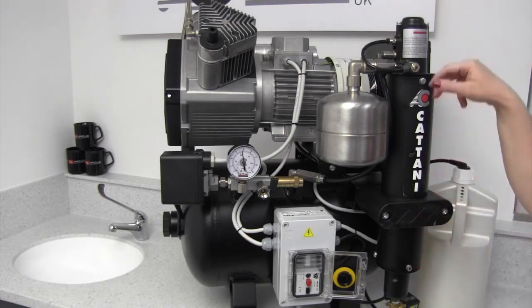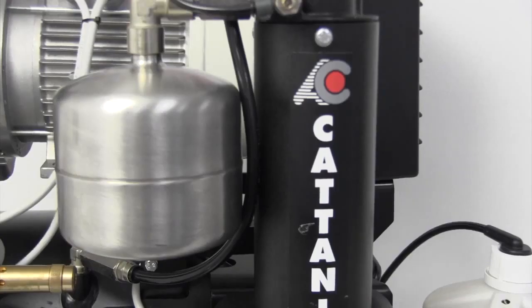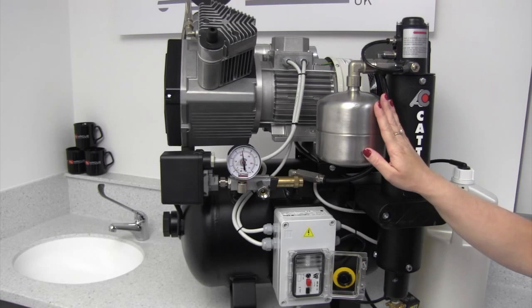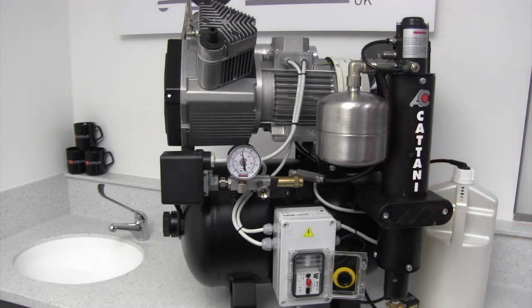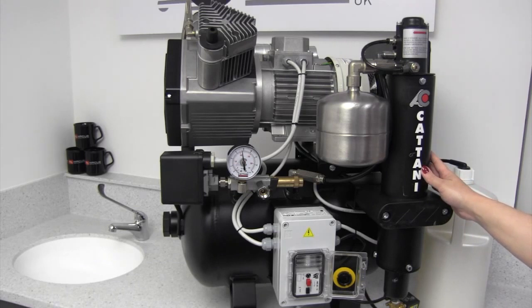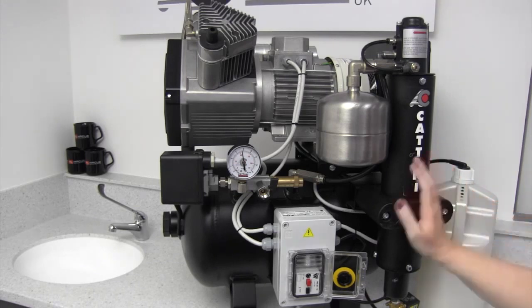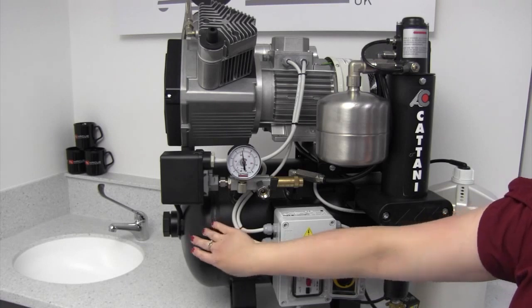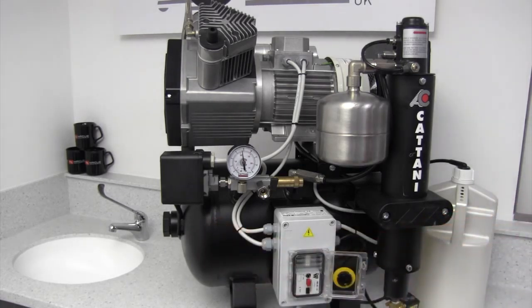The air then rises through the drying column and a small amount of air will be held in the stainless steel receiver. Inside the drying column is a desiccant similar to that found in a new box of shoes, but of a higher grade. The remaining air is then stored in the receiver. The internal surface of our receivers are coated with BioCoat Silver ion technology, which provides permanent antimicrobial protection which is guaranteed.